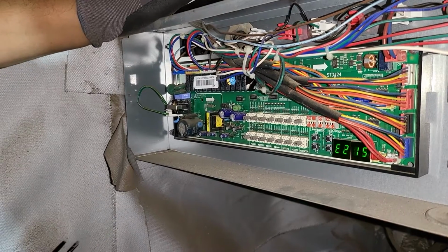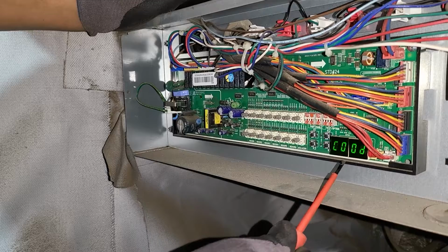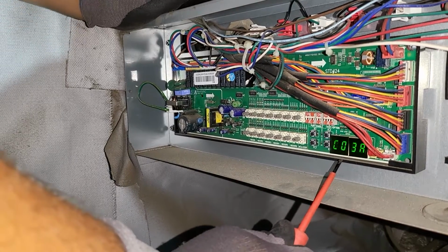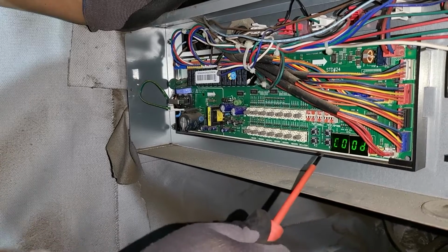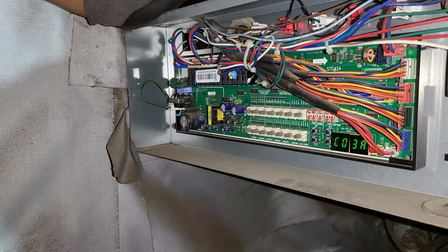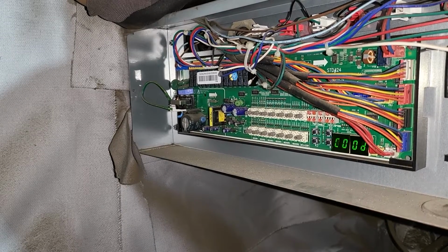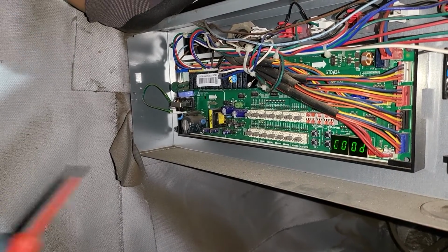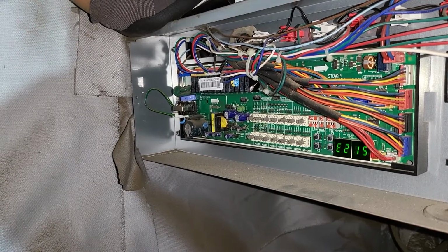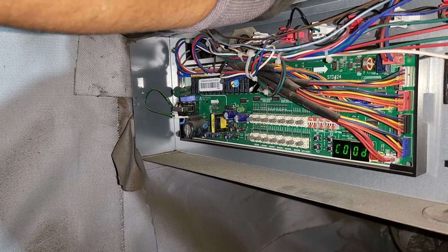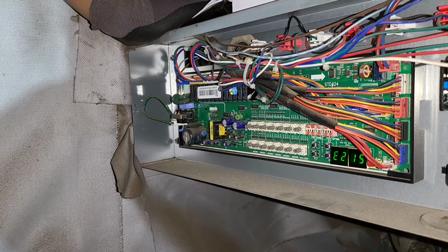Okay guys, it seems we found our problem. First thing that's worth noting is that the 215 error code that we saw at MCU 00, which is the first one, is duplicated here, which is telling you that you're probably going to have a duplicate on this MCU.